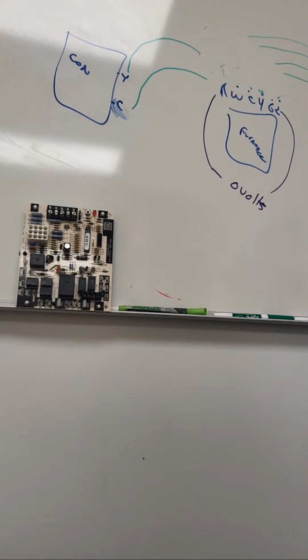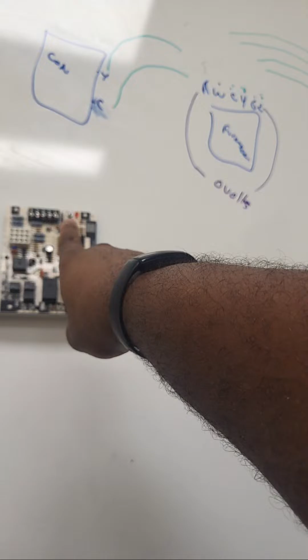So I turned the power off again and reconnected my thermostat wires back to my indoor circuit board, then turned power on, and the light stayed on and the fan turned on, which is good. If I have only my condenser wires disconnected and only my indoor wires connected, and it's running, that tells me two things: first, everything is okay with my thermostat wires inside, and second, something's going on with my outside unit or wires that's opening my fuse.